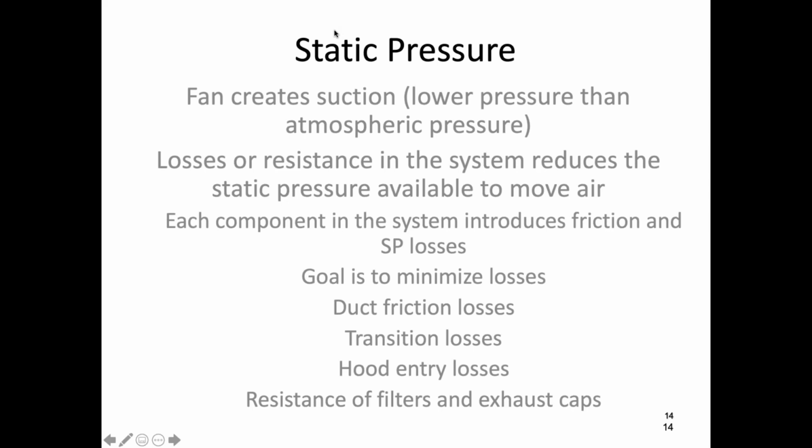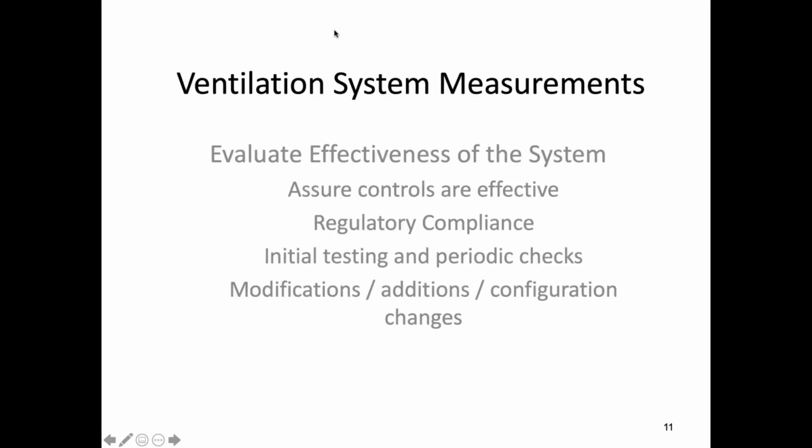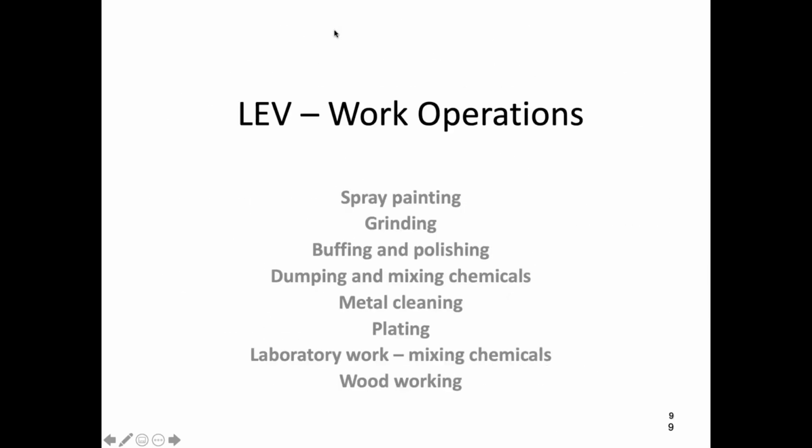It's not always going to be the same amount. It's going to depend on a lot of things. Among other things, it's going to depend on the type of contaminant that we're going to try and capture. Do you think that we need higher velocity? Let's say that we own a nail salon, and there's been a lot of controversy about nail salons and acetone and the other chemicals that they use. Do you think we need higher velocity to capture acetone that somebody's using on someone's fingers to take off nail polish, or do we need a higher velocity to capture material that we're grinding out between bricks? Which one of those two do you think takes a higher velocity?